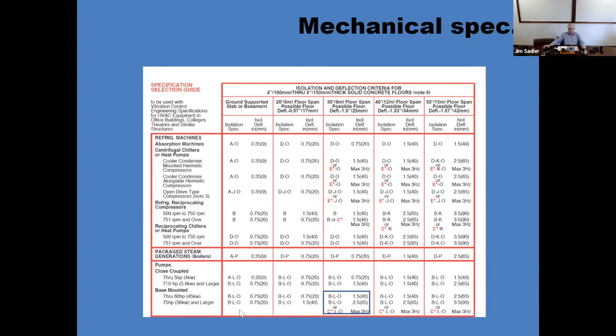And you'll notice that regardless of structural span, the recommended isolation system is the same. The only thing we've changed is the static deflection of the isolators. That's increased with structural span. We're compensating for that structural span by going to higher deflection isolators.